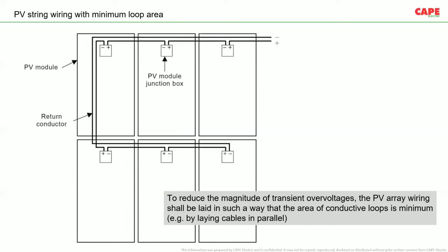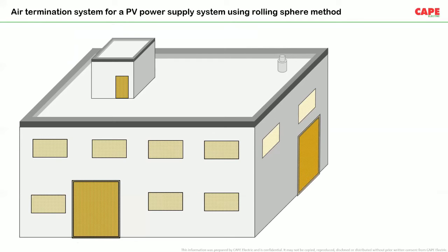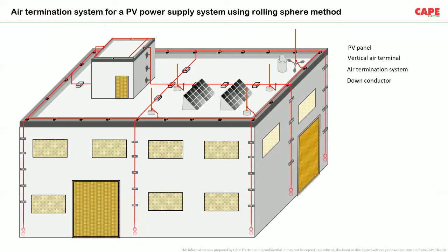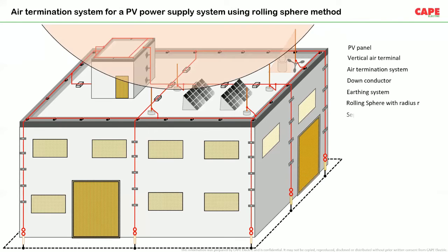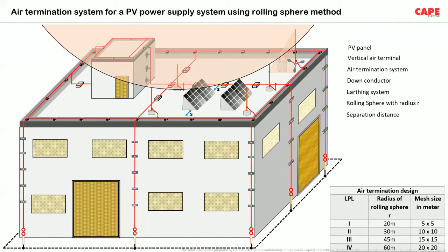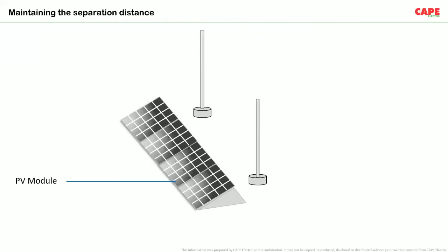So now, coming to lightning protection, of course, the recommended method is in the standard. You have to have a mesh, you have to have individual rods, and you can apply a technique such as the rolling sphere in the air termination, so that lightning is not striking the building or the PV directly.